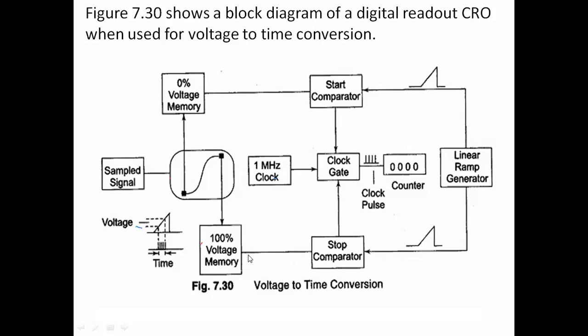The clock pulses pass through the clock gate until the stop comparator produces the stop signal. The stop comparator compares the 100% voltage signal with the ramp voltage. When these two are equal, it produces the stop signal, closing the clock gate. Within the opening and closing of the clock gate, clock pulses are produced and counted by the digital counter. The count obtained is proportional to the time within the given period.